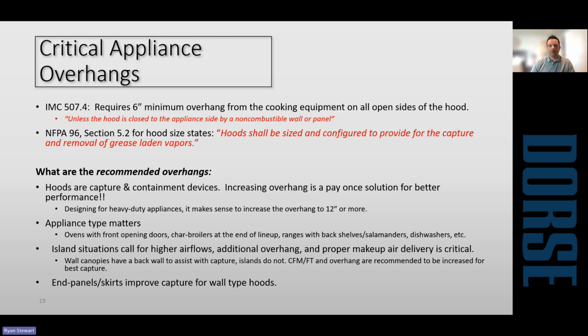What I've seen over the years is the industry's done a pretty good job of getting more front overhang on appliances. It's rare that you see a hood designed with 6-inch front overhang. But as far as the left and right sides of the hood, it's pretty common to just have the 6-inch overhang. In NFPA 96, they don't specify a specific overhang. They just say that it needs to be sized and configured to provide capture and containment of grease-laden vapors.